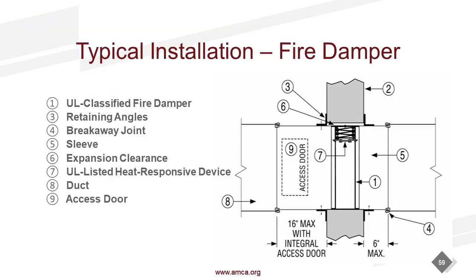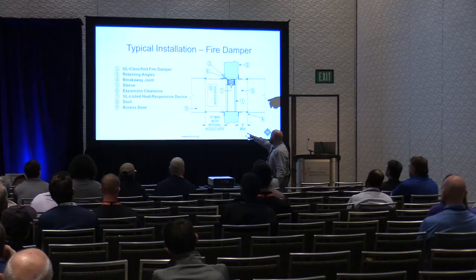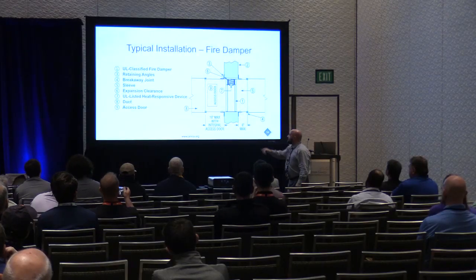Here's your typical installation of that fire damper, that square curtain fire damper. So our number 3 is that retaining angle I just mentioned. So we do a test at UL. It's called the duct drop test. Drop a 500-pound bucket of sand on this breakaway joint, that number 4, that little S clip.